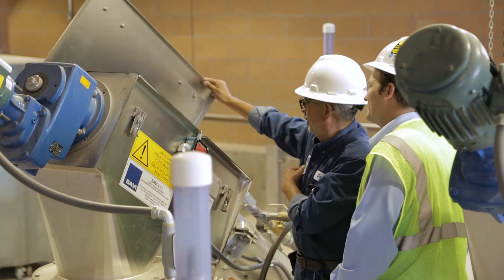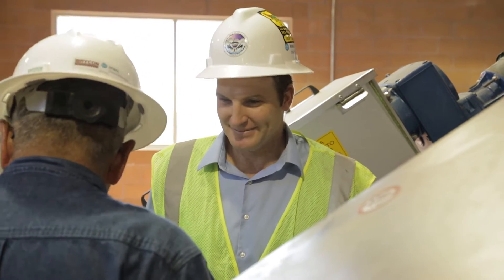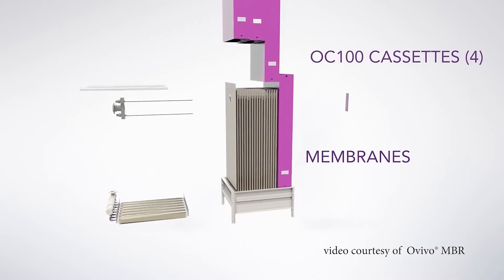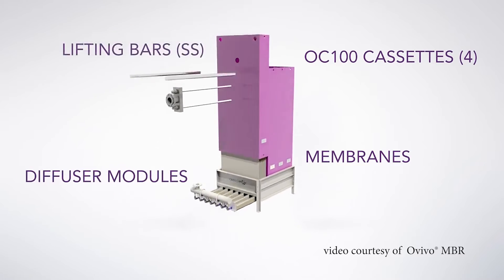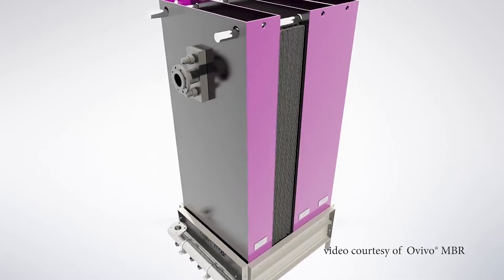This project uses the most modern technologies available for wastewater treatment. When the water comes into the plant it goes through screening, which is typical, but we screen it a little more fine because of some downstream requirements. Then we have a biological process based on aeration, and then we come into the heart of the plant — the membrane bioreactor — which takes the place of traditional clarifiers and filtration, turning very dirty water into crystal clear water using a membrane to filter it.